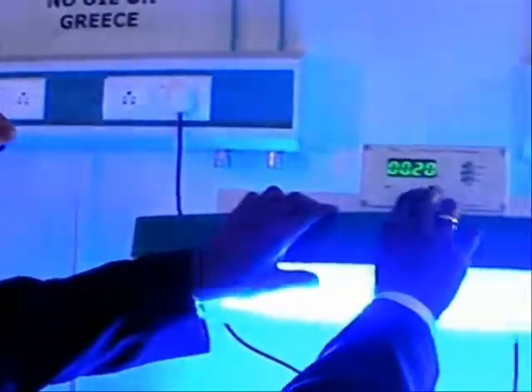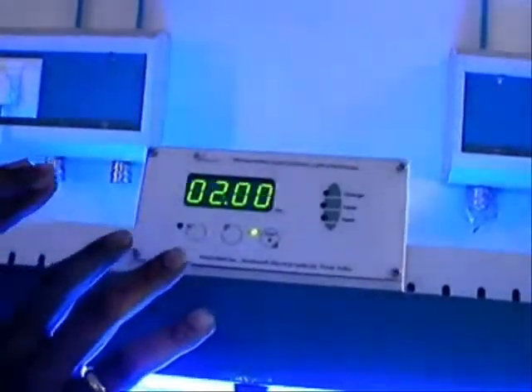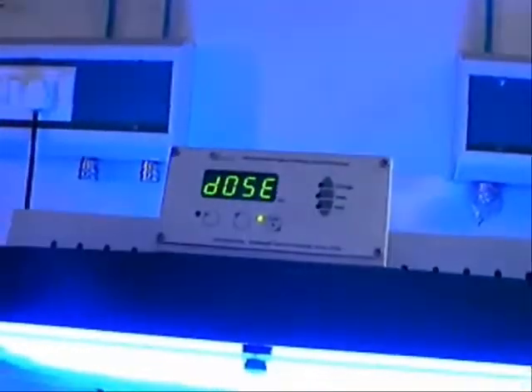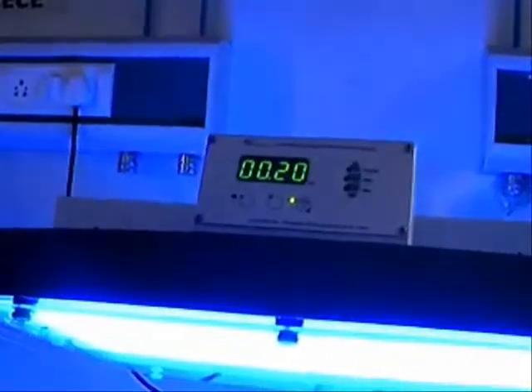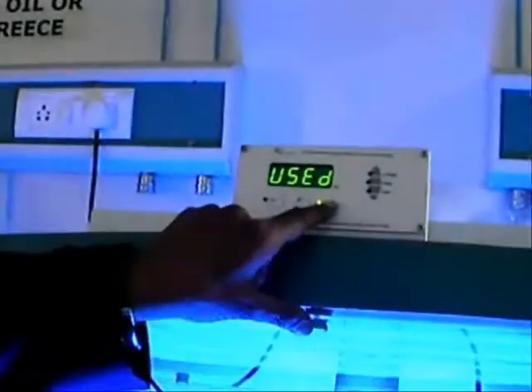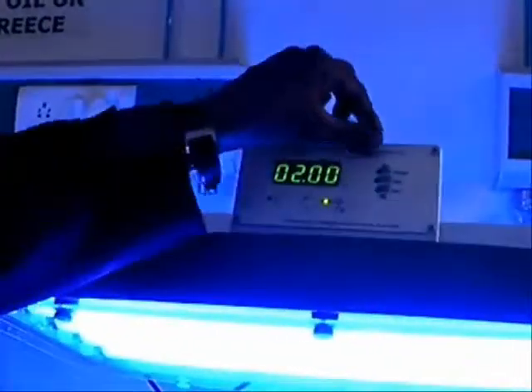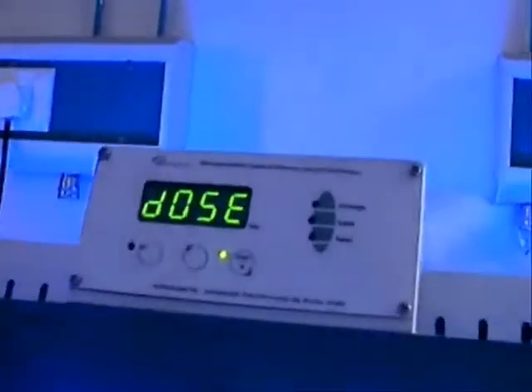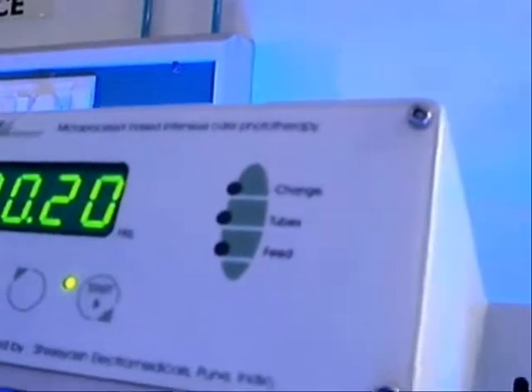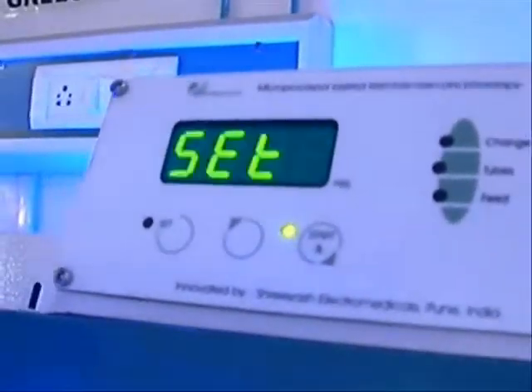For example, now I want to give phototherapy to the baby for say 8 hours. So I can set it by using these up and down keys. It's absolutely simple. You just set the keys. You can set the dose time from 30 minutes to 24 hours. And once the elapsed time is over, automatically the machine shuts off and it gives you an alarm. Plus, it also indicates what the tube usage is. Here you have an indication to change the tubes. Plus, you have a feed alarm which activates automatically after each 2 hours.